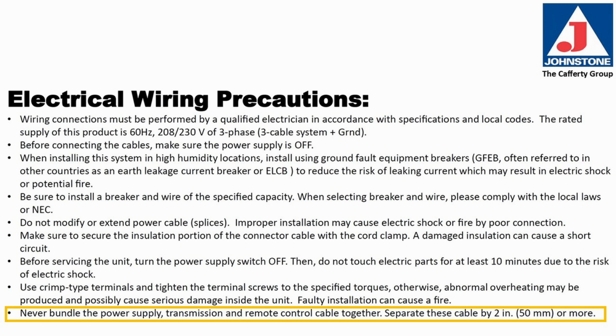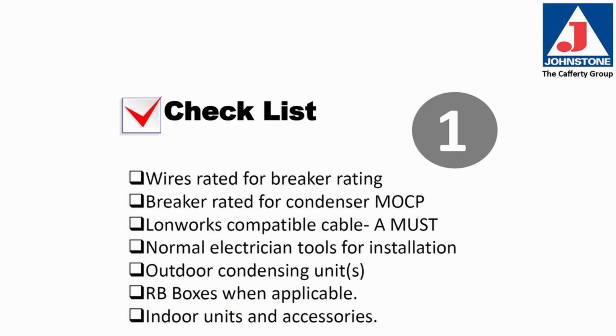Never bundle the power wire, transmission, and/or remote control cables together. Separate by a minimum of 2 inches or more. Here's an electrical checklist. Make sure the wires are rated for the breaker rating. The breaker should be rated for the condenser maximum overcurrent protection. Lonworks compatible cable is a must. Normal electrical tools for the installation are required. Outdoor condensing units, RB boxes when they are applicable, and the indoor units and accessories.